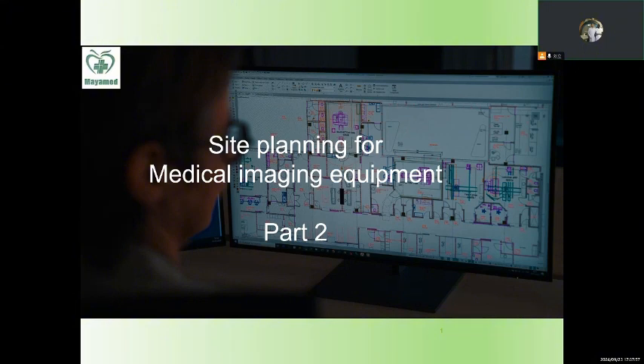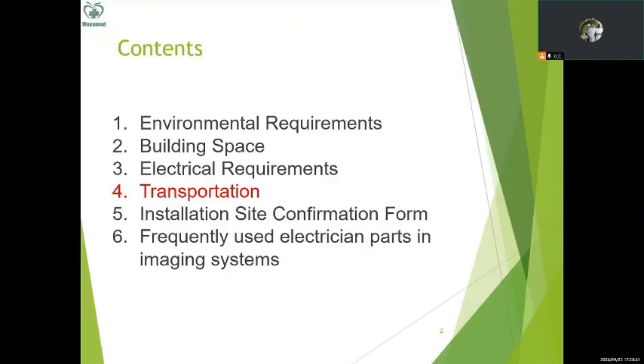Compared with the permanent MRI system, systems like 1.5 Tesla, a CT scanner and a digital X-ray are very easy to transport. The 1.5 Tesla weight is approximately less than 5 tons. For a CT scanner, the weight is less than 3 tons, and for digital X-ray it is mostly less than 1 ton. So compared with permanent MRI, they are much easier. So here, from the beginning, we are going to review what kind of tools are used during the transportation of permanent MRI. We will start from this.